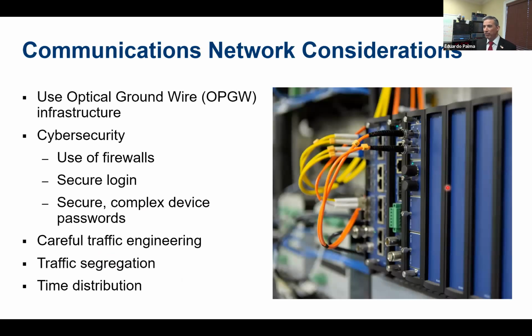This is one of my favorite parts of the story, and it is a very important part because, as I said before, in the beginning in 2011, they were using Ethernet switches to deliver GOOSE messages to trip. But what happened when we went to centralized? We had to upgrade the Ethernet network. This Ethernet network has settings in each one of the devices that need a lot of coordination. And Ethernet, fundamentally, is not a network that always has the same deterministic behavior on packet delivery.